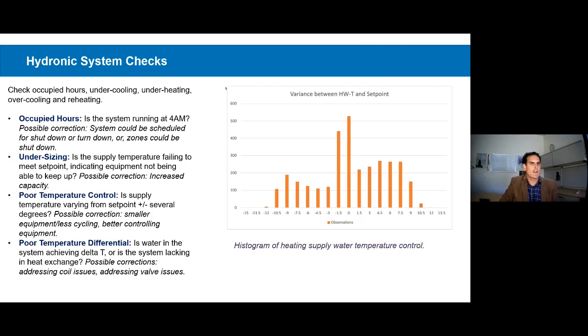And this chart is talking about variance, but this comes into play particularly when we talk about delta T. When we find a poor delta T, we must either accept that and have our new design respond to the delta T that we actually found, or we must change it. And changing delta T can be very difficult. Delta T can never be solved at the equipment in the plant. It's only a function of what's happening in the zones and the valves of the system.